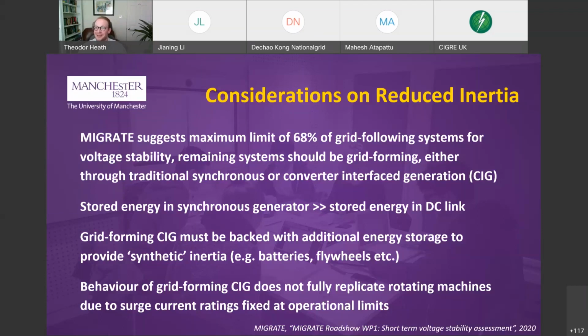The other important thing to mention is that most of our power electronic systems don't have particularly high surge current ratings, if any. So they don't behave the same way as a traditional synchronous generator would, being able to provide maybe 4 or 5 per unit current the instant the frequency starts to drop, for example. So there's still going to be differences in this figure, depending on the mixture of traditional synchronous generation and converter interface generation using grid forming.